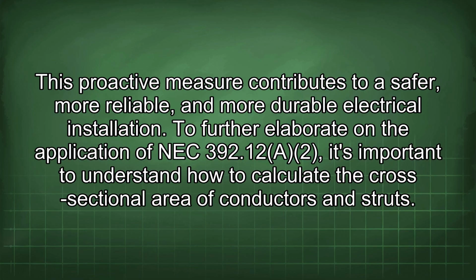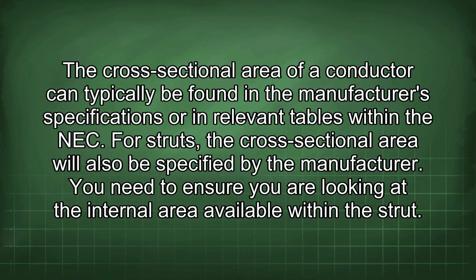To further elaborate on the application of NEC 392.12(A)(2), it's important to understand how to calculate the cross-sectional area of conductors and struts. The cross-sectional area of a conductor can typically be found in the manufacturer's specifications or in relevant tables within the NEC. For struts, the cross-sectional area will also be specified by the manufacturer. You need to ensure you are looking at the internal area available within the strut.